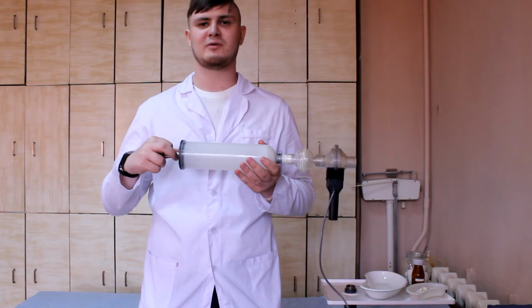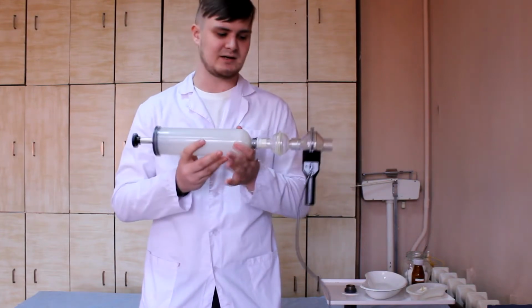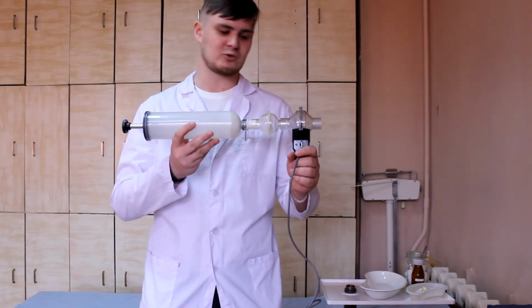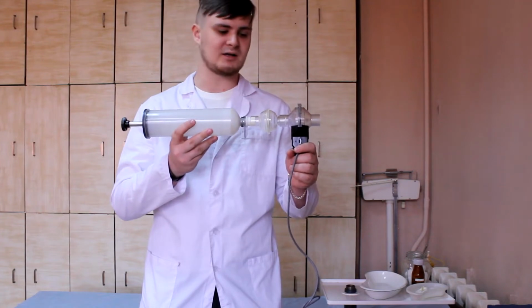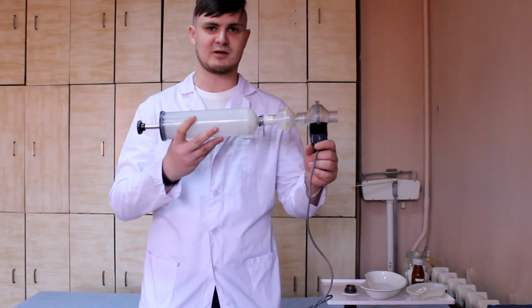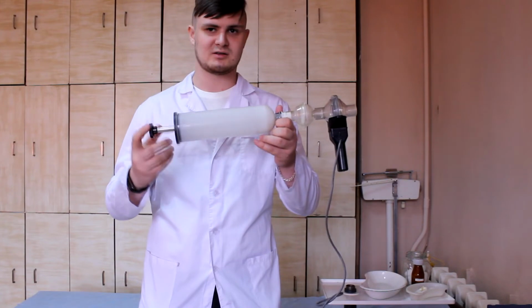It should be noted that during this process you shouldn't hold the handle of the airflow transducer, since it's very fragile. So calibration must be carried out in this position.